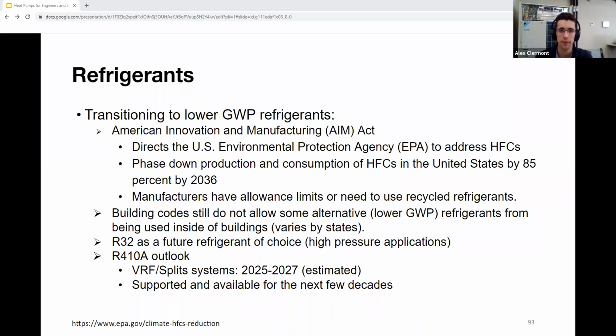Now, one of the issues with building codes is that they do not allow the prime alternative for R410A yet if the refrigerant goes to occupied space. That prime alternative is R32 for high pressure applications. As I mentioned before, I say high pressure because if you're looking at a water cooled cooling only chiller, it's easier to have lower GWP refrigerants, as those are low and medium pressure refrigerants.